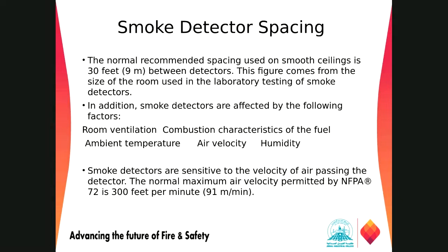So the normal recommended spacing for, now we are moving on to the smoke detector. The normal recommended spacing for smooth ceiling is 9 meters between detectors, right? And this is based on the lab testing of a smoke detector. In actual, it will not be exactly like that, right?